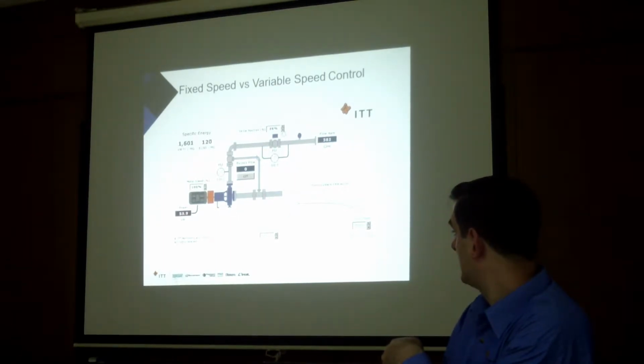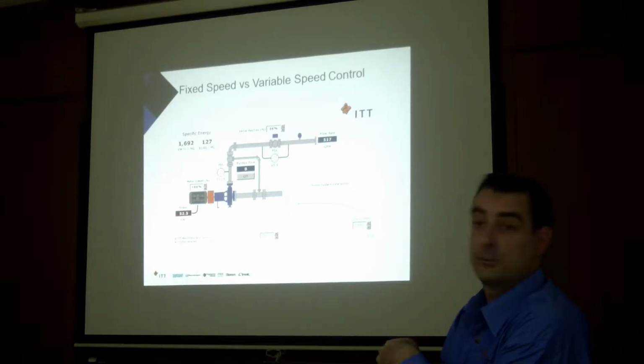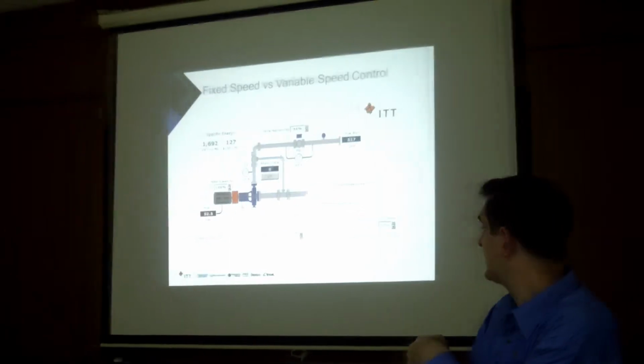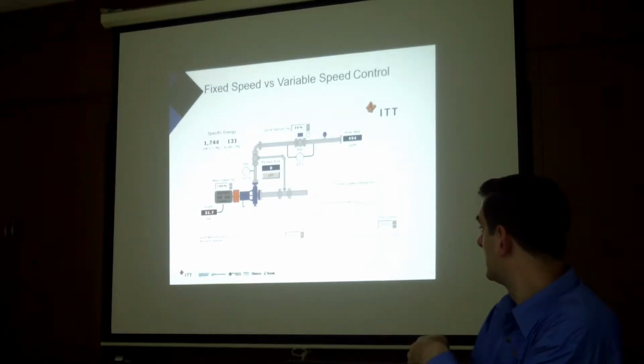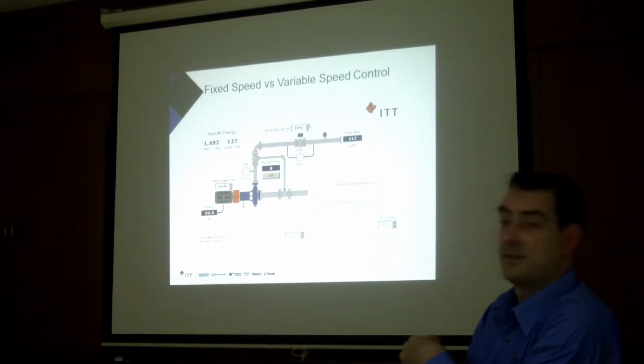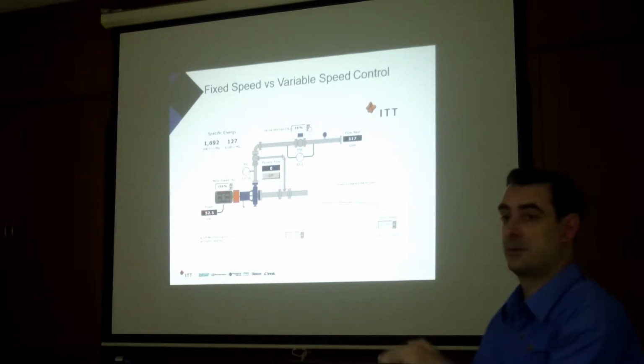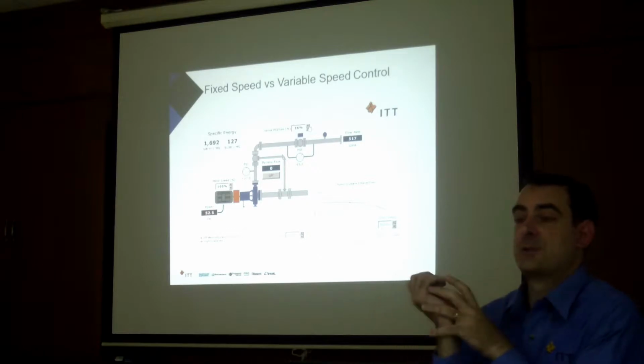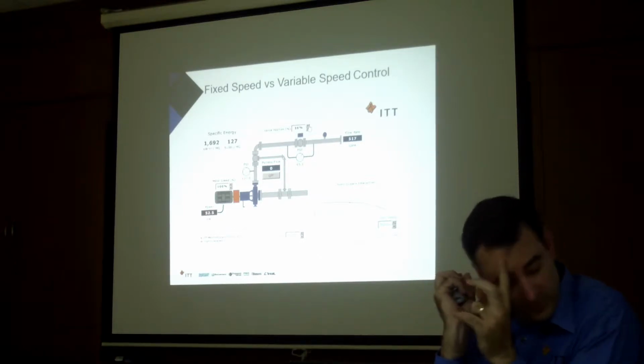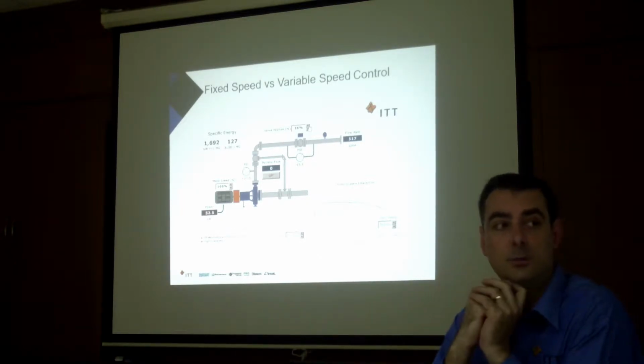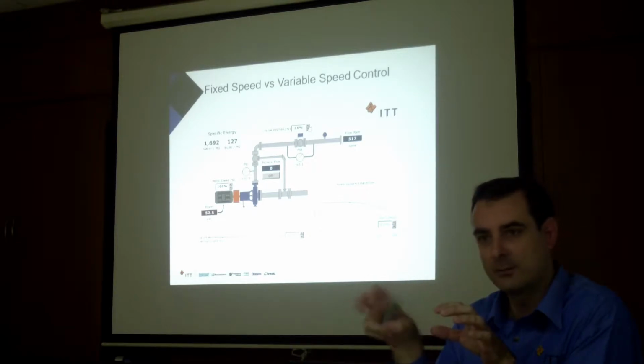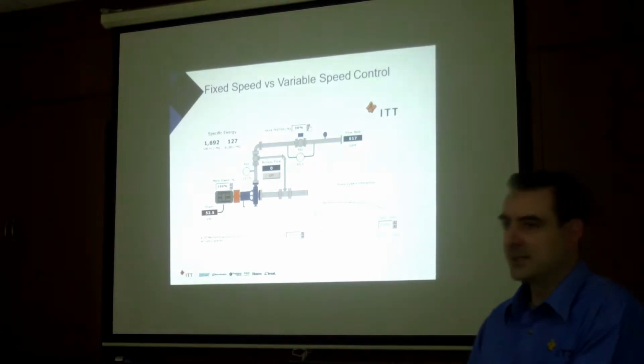As you can see, we keep changing the system curve, and to get the half flow, the power is 35–36%, 52 kilowatt. So I have lots of customers, when I meet them, they said, "Oh, we can save power by reducing the flow."